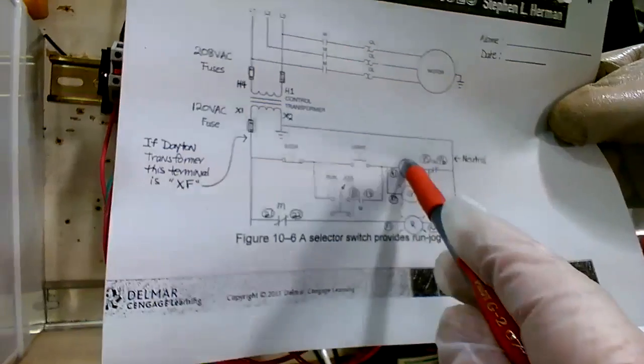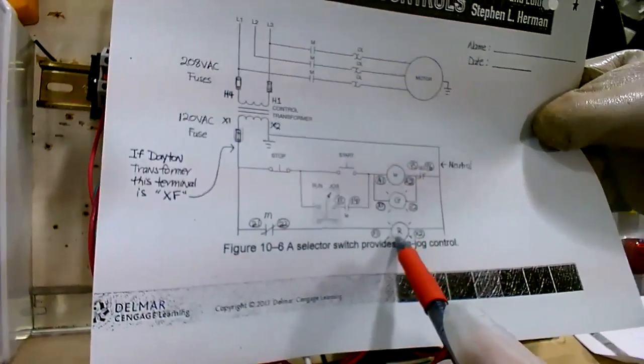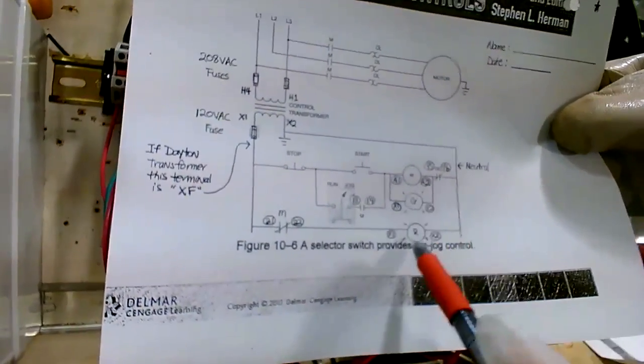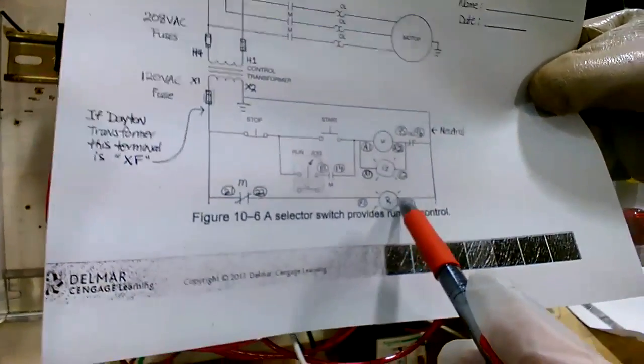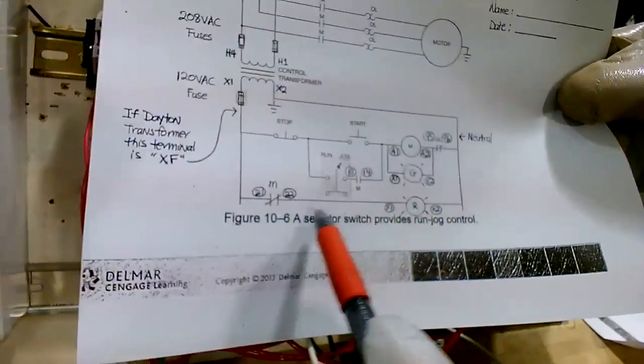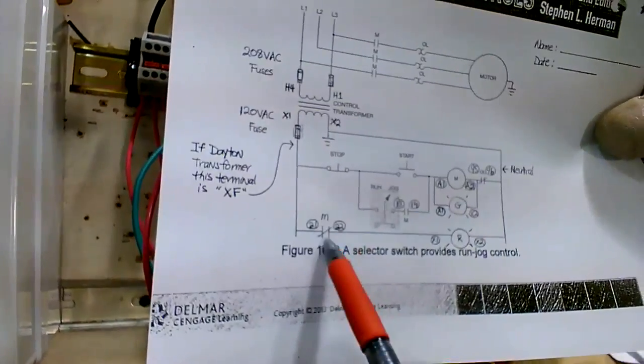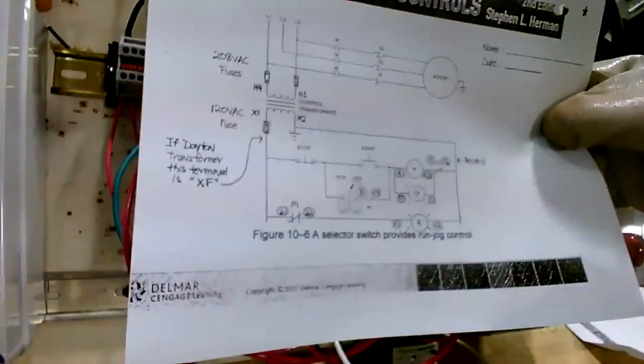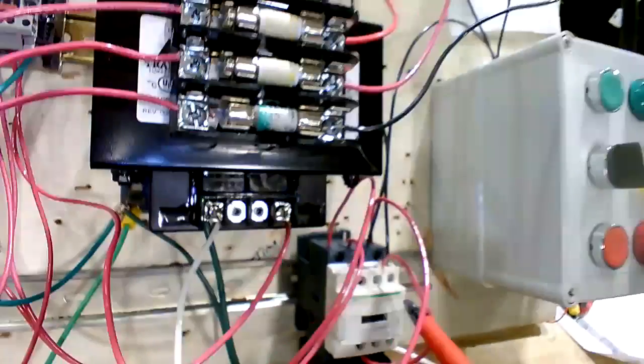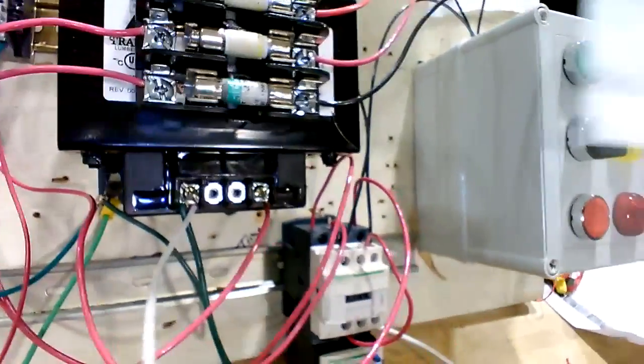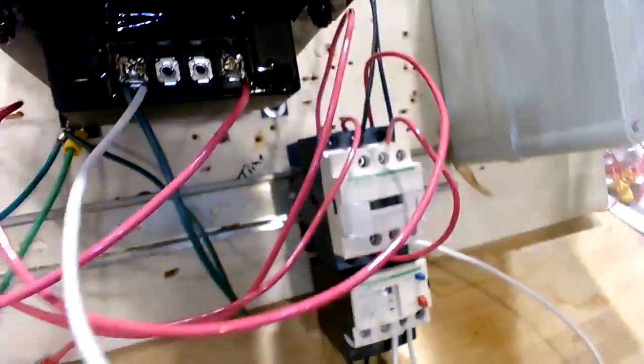Now, the red light. You want the green light on when the coil's on. You want the red light on when the green light is not on. So to make that happen, we take that red light and we come back and we use a normally closed contact. It's mounted on the front of the starter. So if we move that, there's 21, 22 right here. Look closely at it.